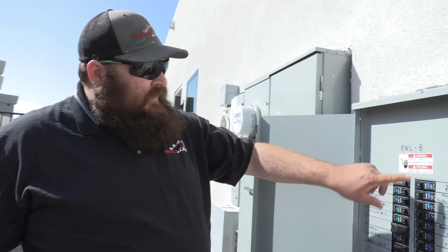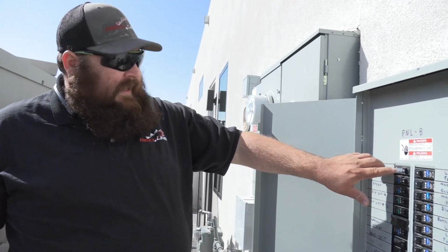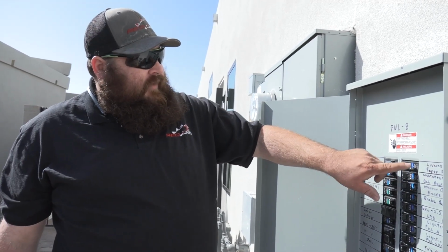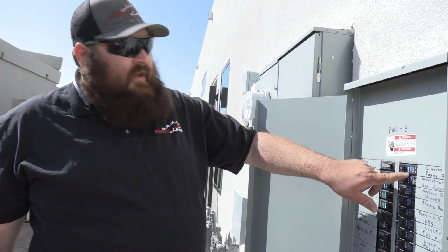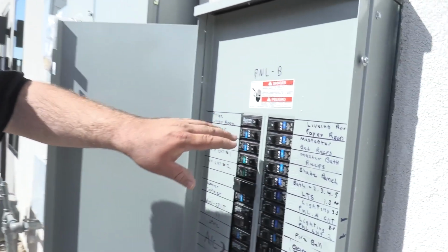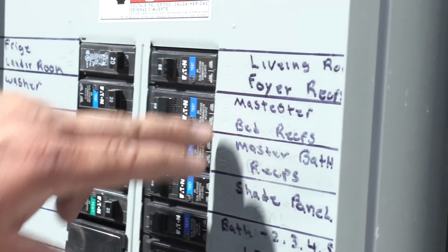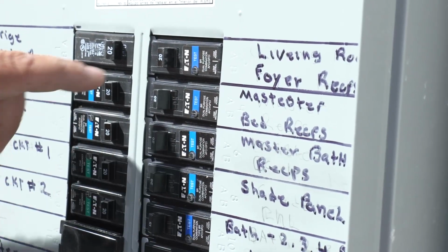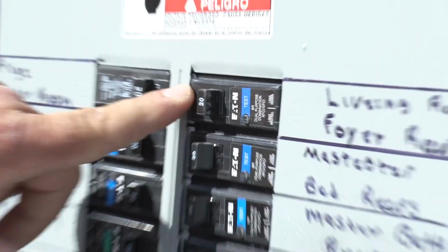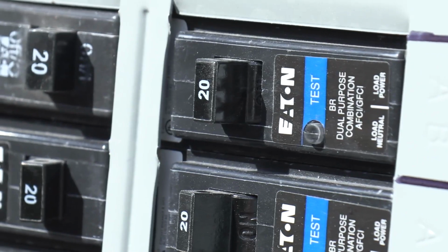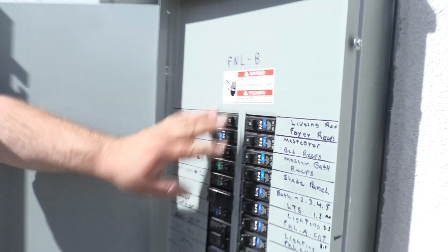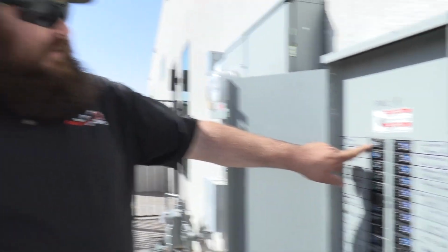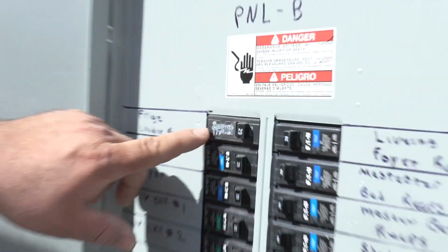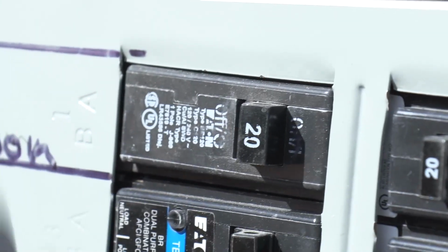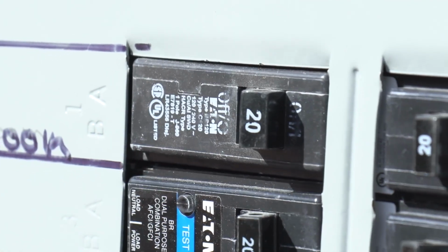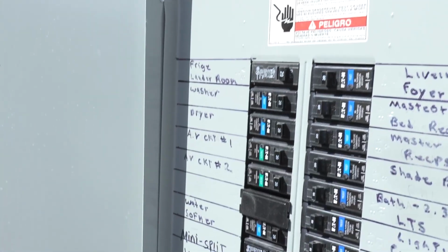As you can see here, there are a few different types of breakers, even though they all say 20 amps and they're single poles. If you look here, the blue ones, these are what we call arc fault breakers. To today's code, when you have a living area, like your bedrooms, your living rooms, they put these arc fault breakers in. It's just an added safety feature. If they sense an arc flash, they'll trip the breaker. Over here you have your standard breaker, and this is just for non-living areas. This is just the regular breaker we put in for everything else. Right here we got our fridge, laundry room, mini splits.